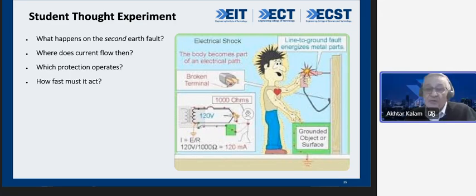Where does current flow then? Okay, the current will flow to the path, it will have a magnitude, and what protection operates? Overcurrent protection will operate. The ground relay, if it's there, will operate, and the directional relay, if it's there, it will operate. How fast must we act? If we don't act fast, the whole system might disappear.